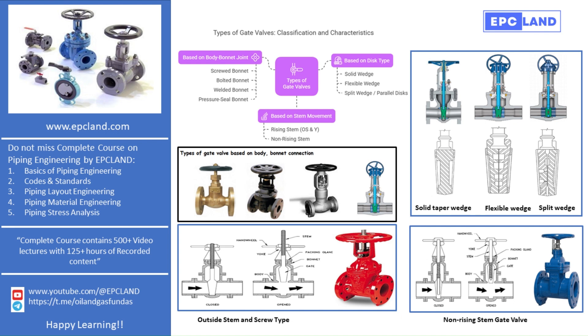Also, in high temperature applications, a solid wedge can experience thermal locking. That means the disc may get stuck between the seats as the metal expands due to heat.